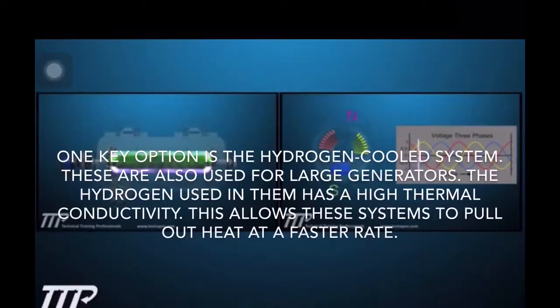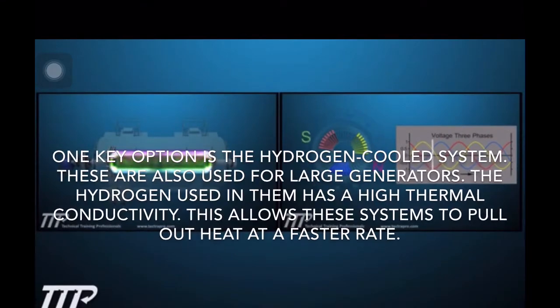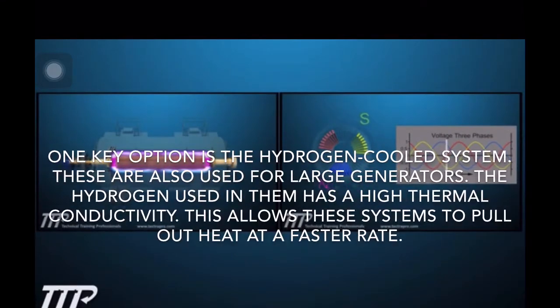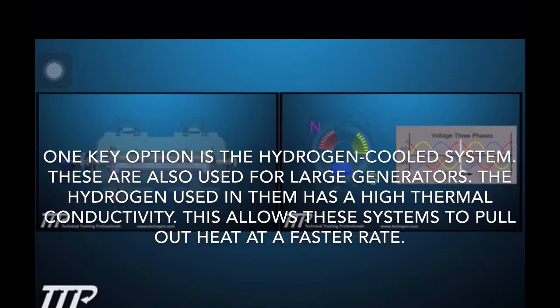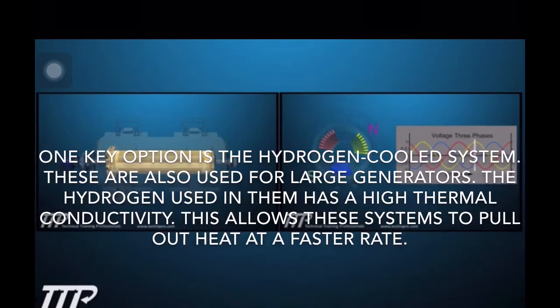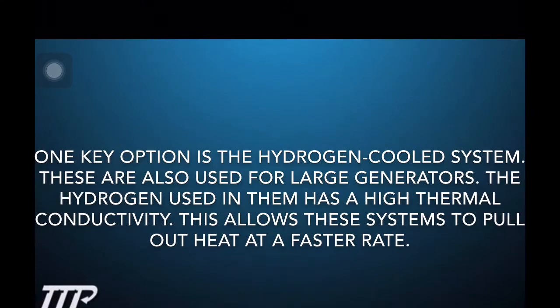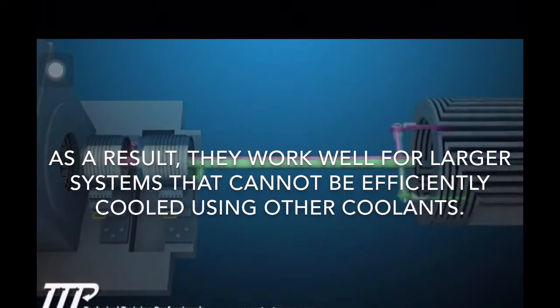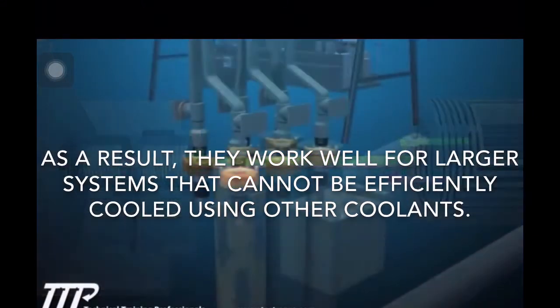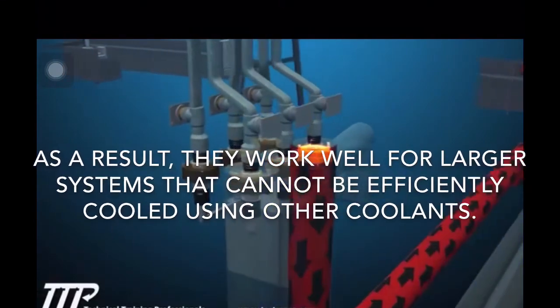One key option is the hydrogen cooled system. They are also used for large generators. The hydrogen used in them has a high thermal conductivity. This allows the systems to pull out the heat at a faster rate. As a result, they work well for large systems that cannot be efficiently cooled using other coolants.